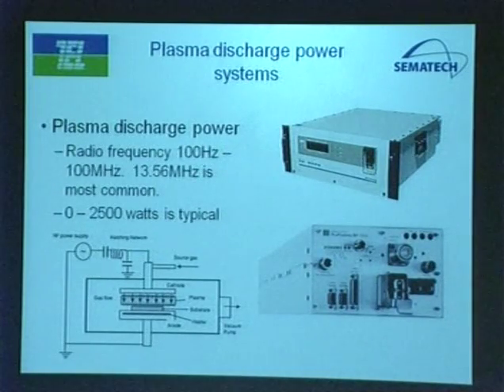Now you need some power to ignite and generate plasma, so we generally use RF discharge or RF power. RF is like AC, only at very high frequency. In this room, all electricity is 60 hertz; in plasma systems, we generally operate from 100 hertz to 100 megahertz, but 13.56 megahertz is most common. Actually, 15 years ago, we only had 13.56 megahertz RF. Can you guess why the industry used 13.56 megahertz for 30, 40 years? The answer isn't technical, it's just something else.